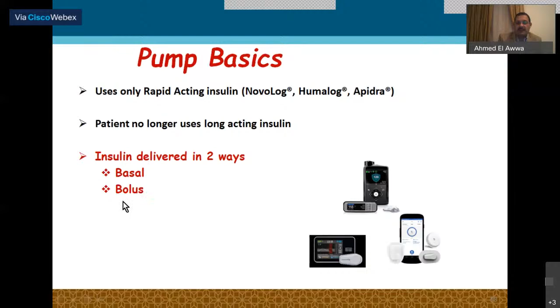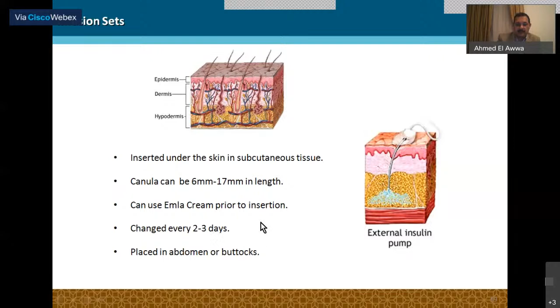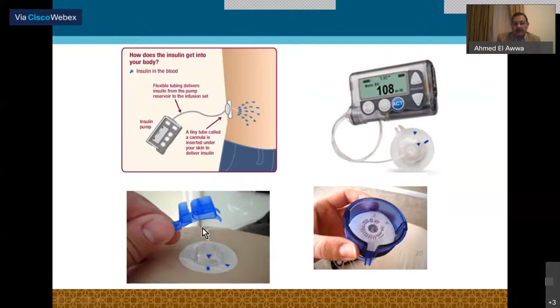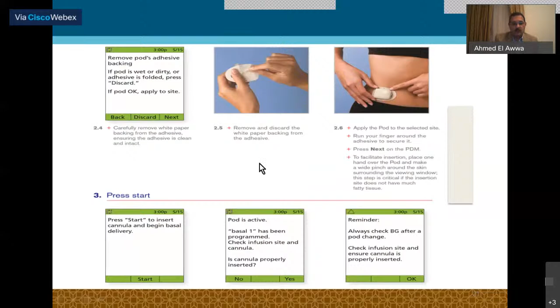So the subcutaneous part is the indwelling catheter. It delivers insulin subcutaneously as a continuous infusion, so it's not bolusing, and a lump of insulin will not accumulate here. It's continuously infusing, and this cannula is changed on average every 3 days. Sometimes in infants, we might need to change it every 2 days. This is the way of insertion. The inserter might use a needle, but the needle will not stay in the body of the child. So we remove the needle after application, and here it is attached to the tube. And some other pumps, called patch pumps, have no tube at all. It just sticks to the body, and then you initiate the pump from the controller, the remote control, and the delivery of insulin will start. There is no tube, and both are available on the market.